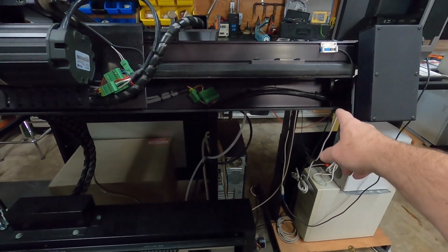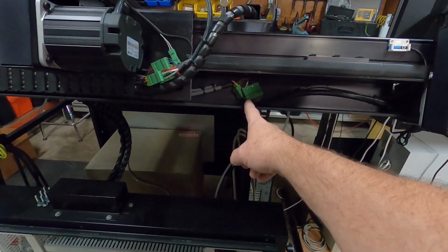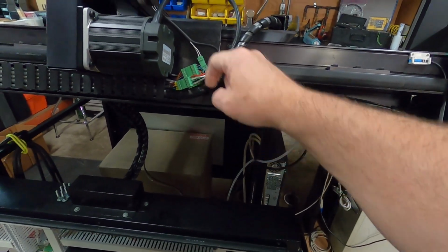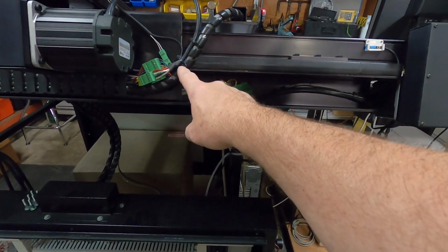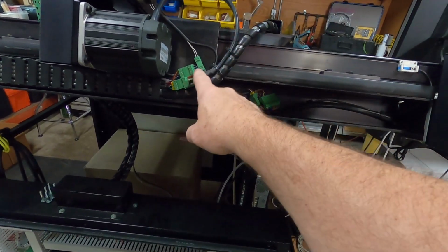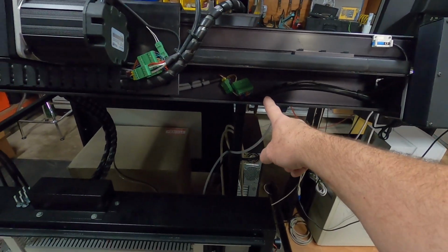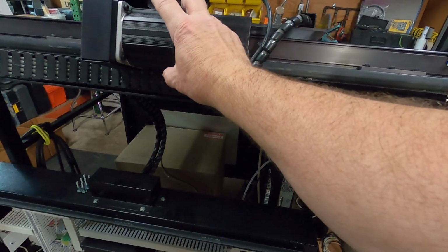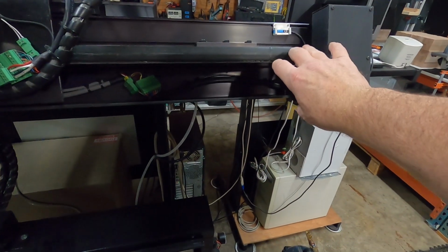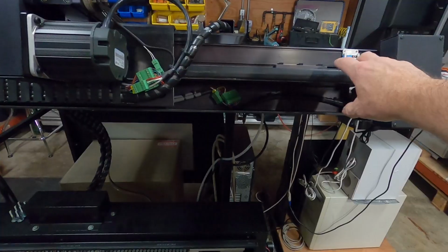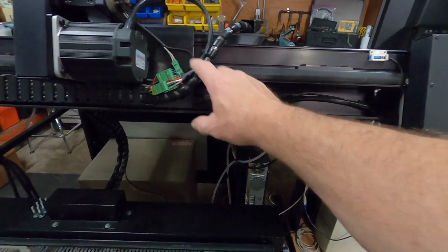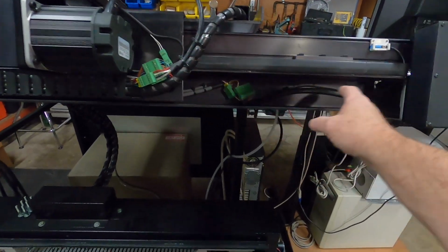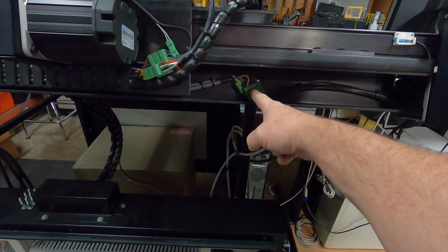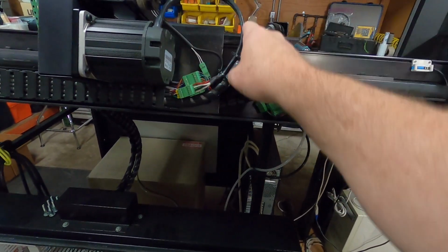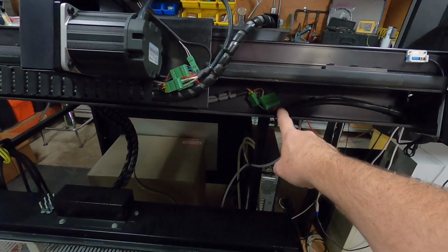This is about 18 inches of wire here, or maybe a foot, but the length of wire here and here should be the same, because someday you might need to swap this motor with that motor for testing purposes, and you won't want this one to have too short a wire so that when you put it over here it can't reach there. So keep this length the same—about 18 inches of wire.